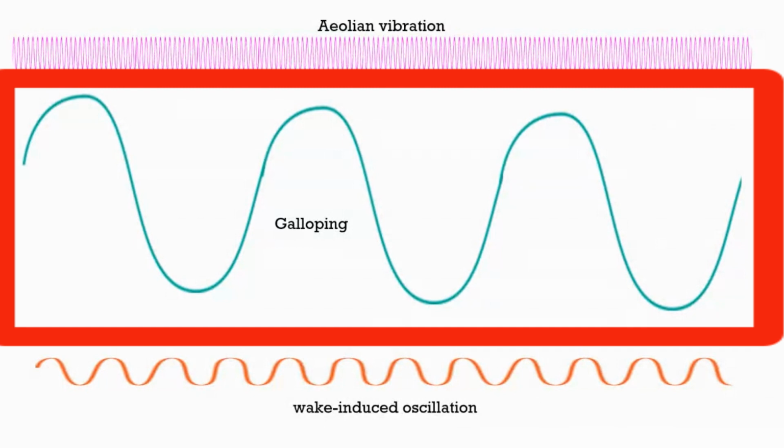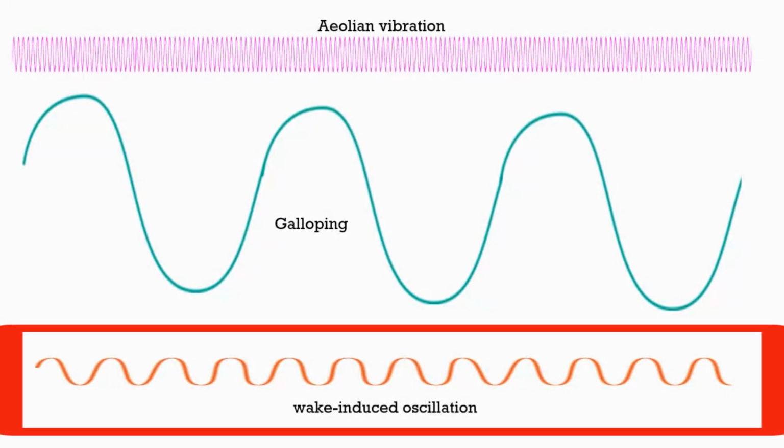Galloping has a high amplitude wave, measured in meters, but the frequency is very low, around 3 Hz. But this galloping is the most severe one. We'll see the video, we'll see everything related to the physics of this. Amplitude can be measured in the range of meters. Then we have wake-induced, with a frequency around 10 Hz. The amplitude is in the range of centimeters.